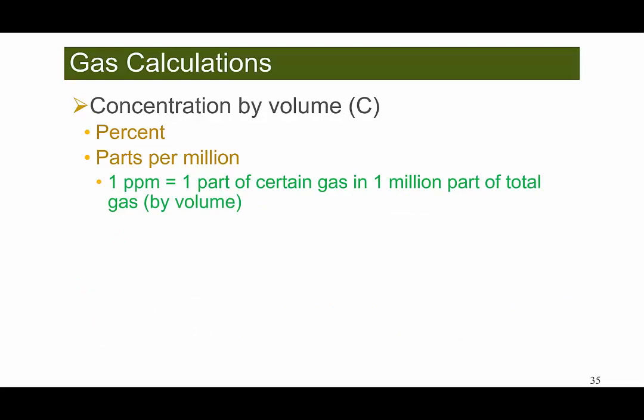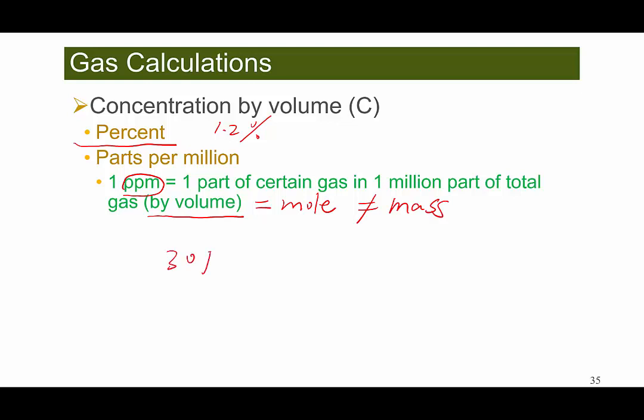Let's talk about some basic things we need to know before we go into the gas math. When doing gas calculations, most of the time we use gas concentration. It can be in percent, say 1.2% of CO2. Sometimes if the concentration is low, we use parts per million. One part per million is one part of a certain gas in one million parts of total gas — this is by volume, which equals by mole, but it is not equal to by mass. By default, if we say 30 ppm without specifying, it is by volume.